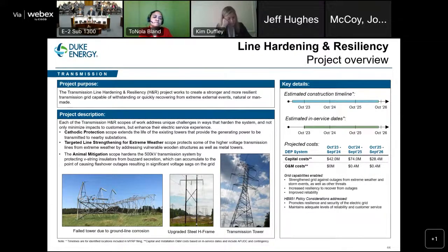So again, we're targeting specific poles that we've identified as degraded. We're upgrading them to steel, and in most cases, we've greatly reduced the chance of that pole failing during an extreme weather event or other scenario. Transmission towers are very similar. We're targeting specific types of transmission towers that are susceptible to failure. In these cases, the degradation is not just at the ground level, but up in higher parts of the tower, and we can't arrest the corrosion or the degradation through cathodic protection. So we're targeting replacement. I'll talk about a specific example of that on the next slide.